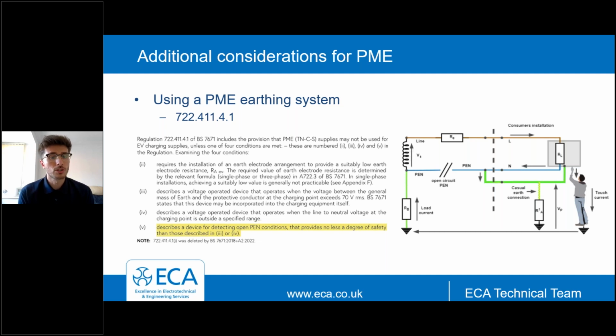Indent 2 looks at adding an additional earth electrode to the PME earthing arrangement, and the image to the right of the screen is relevant to this. This requires the earth resistance of the electrode to be added to be at a very low value, which in most types of installations is very difficult and impractical to achieve, due to maybe the type of ground, or the difficulties of even having to bury an earth electrode. So it's unlikely that it's used, but it is a possibility.